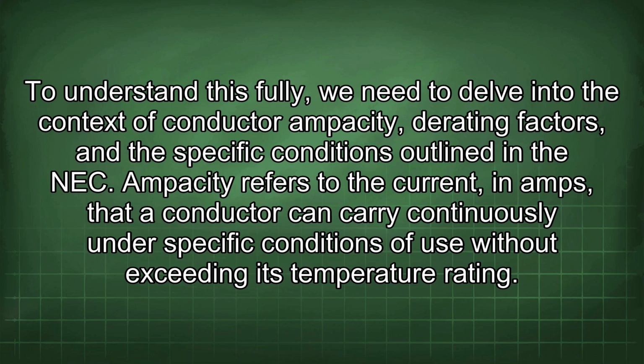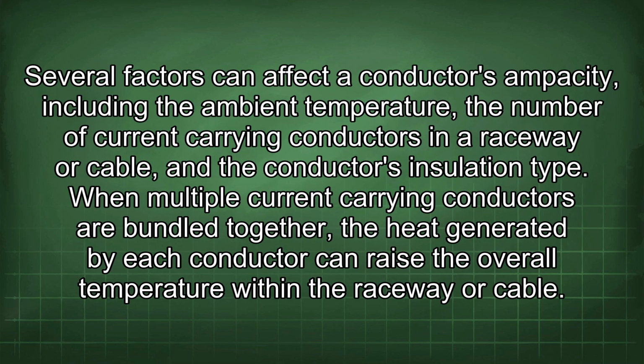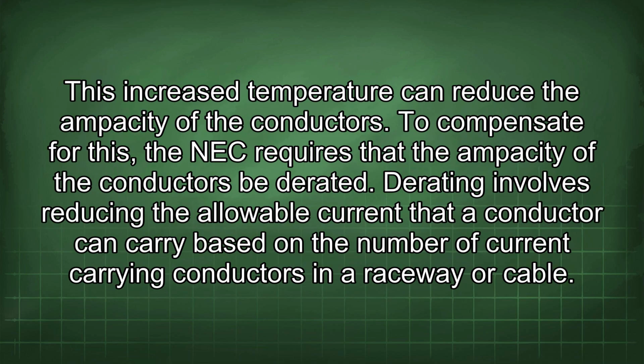outlined in the NEC. Ampacity refers to the current, in amps, that a conductor can carry continuously under specific conditions of use without exceeding its temperature rating. Several factors can affect a conductor's ampacity, including the ambient temperature, the number of current-carrying conductors in a raceway or cable, and the conductor's insulation type. When multiple current-carrying conductors are bundled together, the heat generated by each conductor can raise the overall temperature within the raceway or cable. This increased temperature can reduce the ampacity of the conductors.